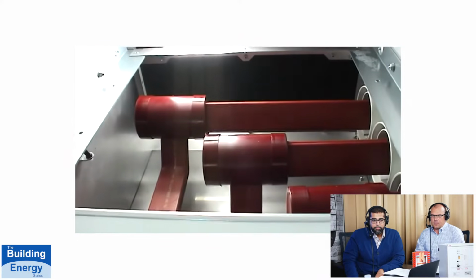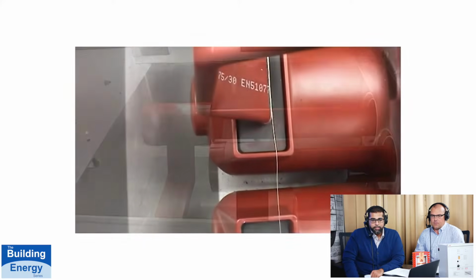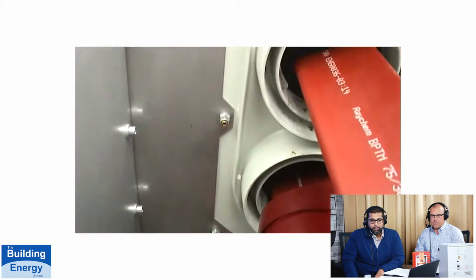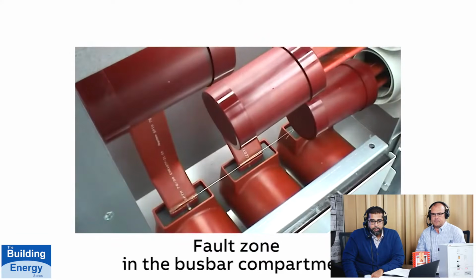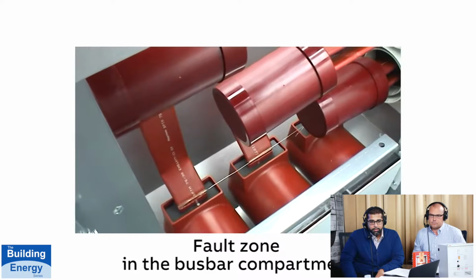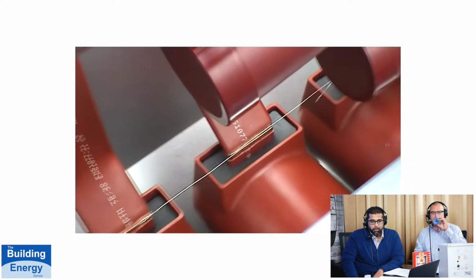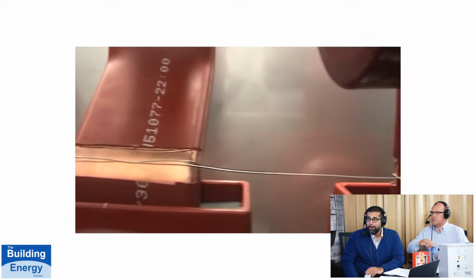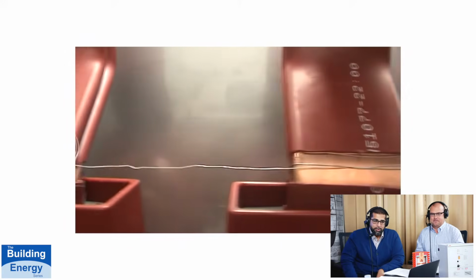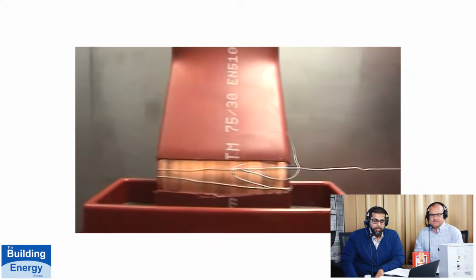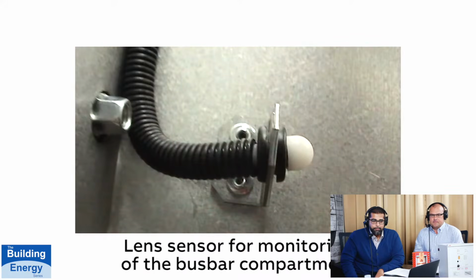So you see here, the primary switching elements are connected to the main bus bar. What they've done here is simulate a three-phase fault between the bus bars. You see that little string, the wire that's connected to all three phases. This would not be the case in a normal setup. You don't want to have anything there. But because this is an arc flash, internal arc test, that's how they do it.